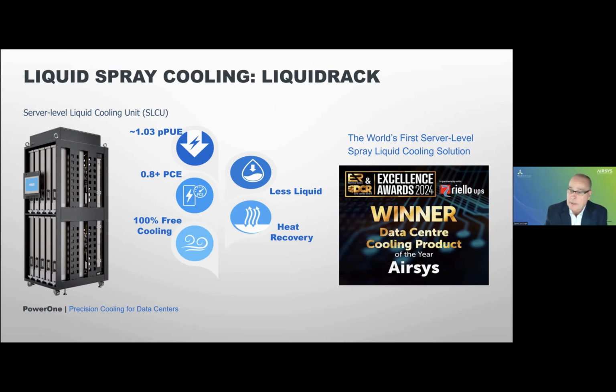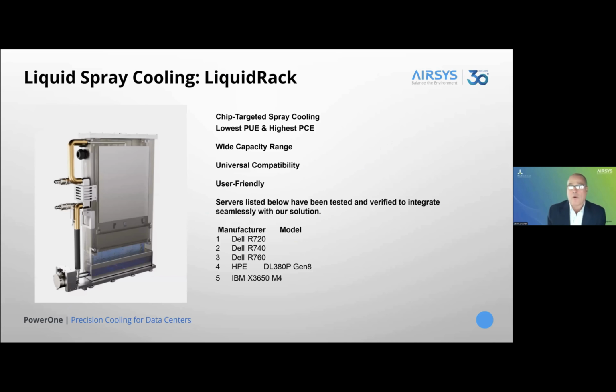This product is one of those products that's really hitting in the industry in a different category. The cassette itself, as you see here, again, is a spray. What you are looking at is at the bottom is a little tub that catches the dielectric fluid as it showers over the GPU or CPU. It is then moved into a pump, which then moves it into the heat exchanger, where the facility water, which is on a separate loop, removes the heat, and then it's just pushed right back into the chip. So it's that evolving.